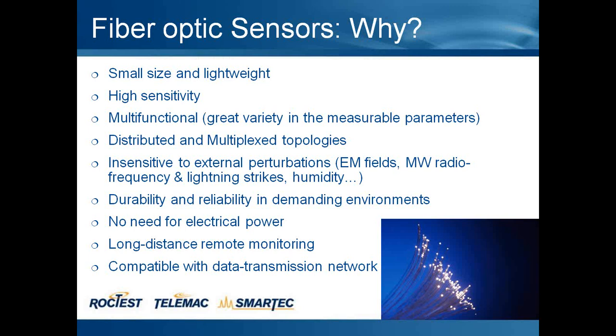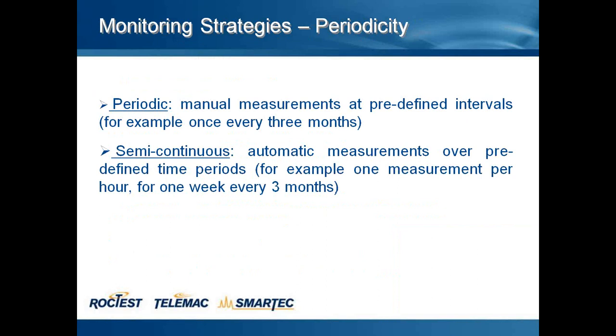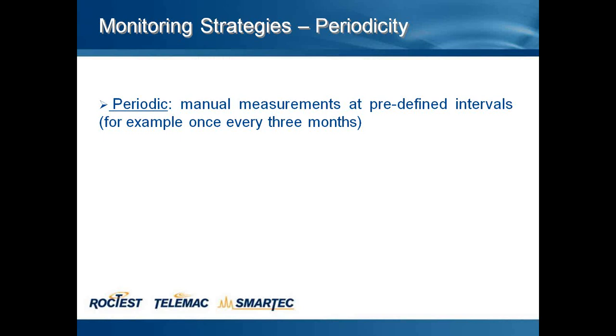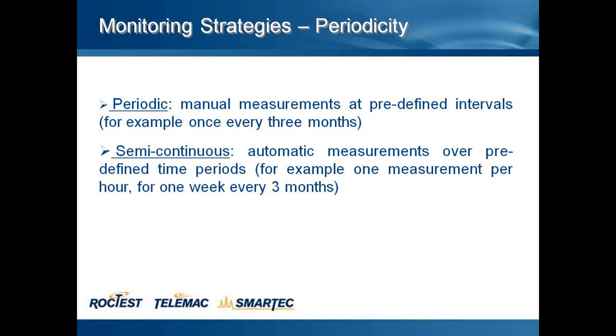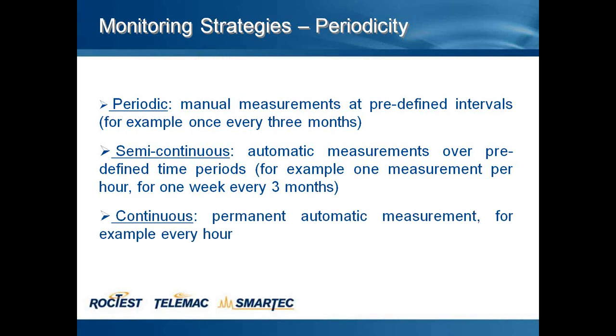Regarding the monitoring strategy and periodicity: we can have periodic measurement — manual measurement at pre-defined intervals, for example once every three months. Semi-continuous automatic measurements over pre-defined time periods, for example one measurement per hour for one week every three months. Or continuous permanent automatic measurement, for example every hour.